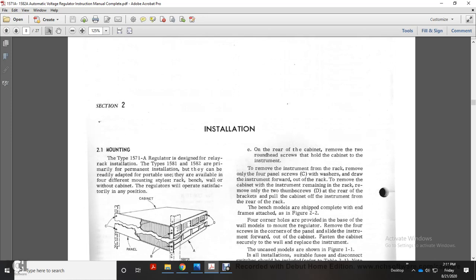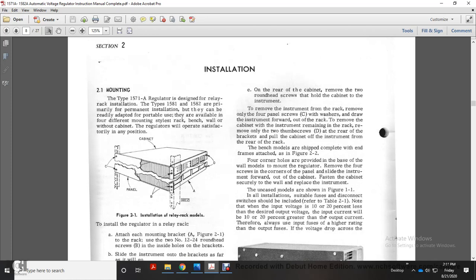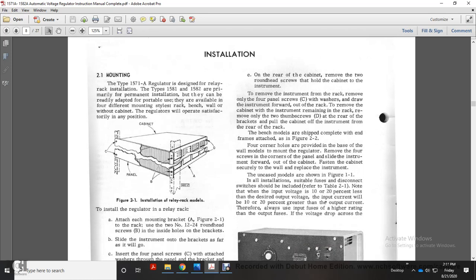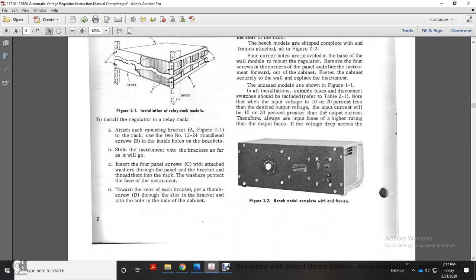Alright, section 2, installation. Mounting. The type 1571A regulator is designed for relay rack installation. The 1581 and 1582 are primarily for permanent installation, but they can be readily adapted for portable use. They are available in four different mounting styles: rack, bench, wall, and without cabinet, and the regulators operate satisfactorily in any position. Figure 2-1 shows the relay rack installation with panel and cabinet. To install the regulator in the relay rack, attach each mounting bracket A, figure 2-1, to the rack with two number 12-24 round head screws B in the inside holes of the bracket.